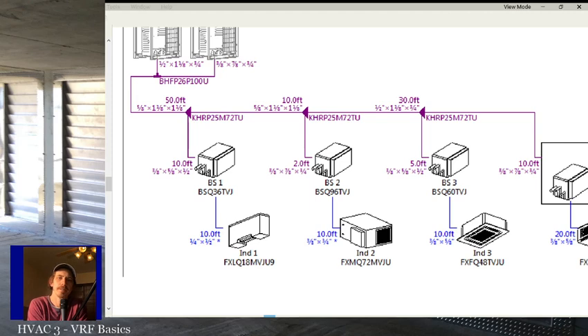It's better practice. It's just like anything else. Ideally, you keep the line set as short as possible, right? It becomes much more critical when you're not keeping the line set as short as possible to one unit. You're keeping as short as possible to 50 units. So don't worry so much about adding a couple 90s to make it look good. If you need to put in a 90, try and bend the copper to make the 90. Don't use an actual braze 90.